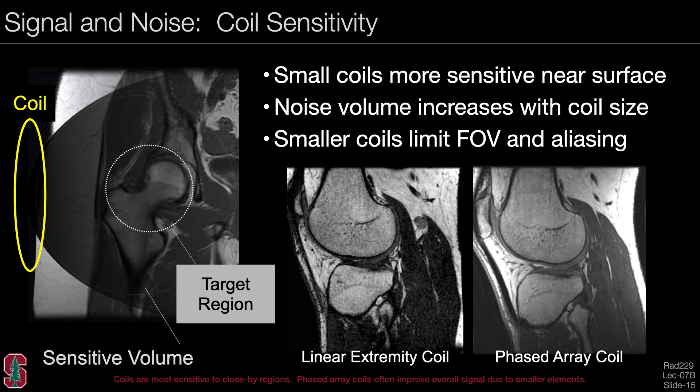Another important coil consideration is the comparison between linear, quadrature, and phased array coils. Going from a simple linear birdcage coil to a quadrature coil should give approximately a square root of 2 improvement in SNR. Phased array coils will do similarly or even better than quadrature coils. Here you can see a dramatic improvement in SNR between a linear extremity coil and a phased array coil with exactly the same sequence parameters.